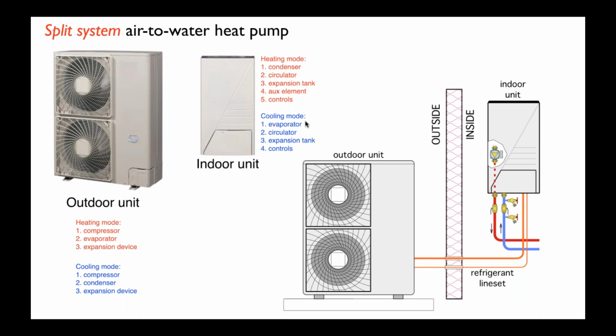equipment. When you put the line set in, you need to evacuate it with a vacuum pump, and then you open service valves. There is enough refrigerant in the outdoor unit to cover so many feet of line set, typically 25, maybe 30 feet of line set. If you're going farther than that, you're going to have to add. Most of these are R410A refrigerant.